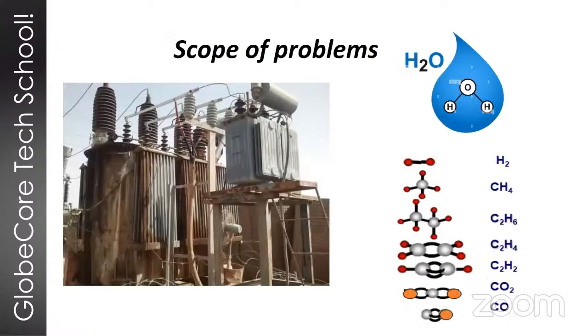Right. So in our past webinars, and we've had a few already, we already discussed insulation as one of the most vulnerable parts of a transformer. And in fact, a transformer lifetime is defined by the lifetime of its paper insulation. And in its own turn, paper insulation is impacted by water a lot because water causes destruction of cellulose molecules and promotes reduction of dielectric strength. And so it's very important to remove water from the transformer as much as possible and perform this procedure periodically during its entire lifetime. Next slide, please.